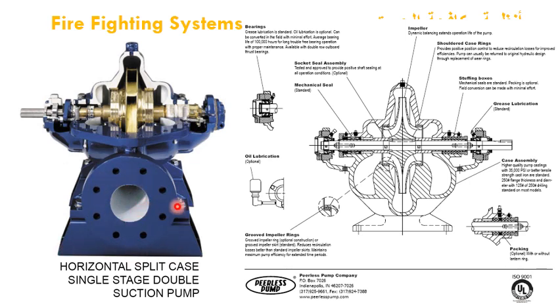And this is the base of the pump, and this is the body of the pump affixed securely with these bolts to the base as shown. Also here we can see the construction details drawings for the same horizontal shaft and its bearings from both sides as mentioned before, with the grease lubrication here, and the stuffing box, and the impeller finally is affixed with a feathered key to the shaft of the pump, which will be feathered key also from this side to the pump driver, either an electrical motor or diesel engine.